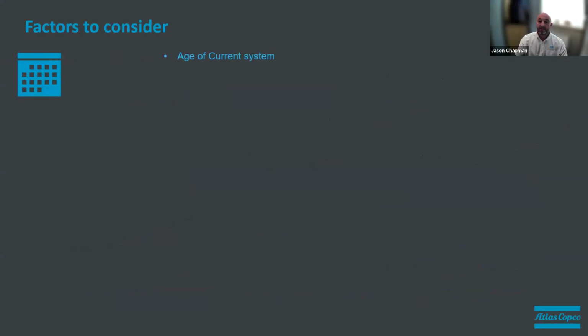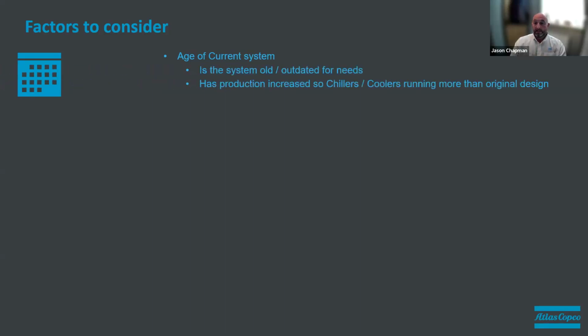We need to consider the age of the system. Is the system old? Is it outdated for its needs? Looking back at some of the poll questions early on, a few came through stating that the production or the manufacturing process has increased since your chiller system has been in place. So potentially what you are doing there is using your backup system or running the system inefficiently. You're running it flat out, you're not getting the cooling that you need, which, as we go back to the previous slide, could have a detrimental effect on the outcome of your production, your processes, or your widgets that are coming off the line. So, is the system old, new, or outdated? Has production increased? As we said before, the chillers and coolers are running more than original design spec.